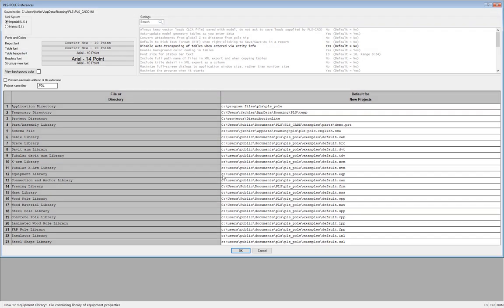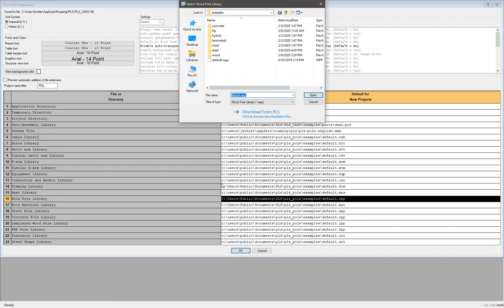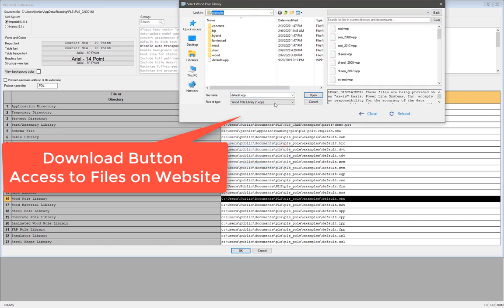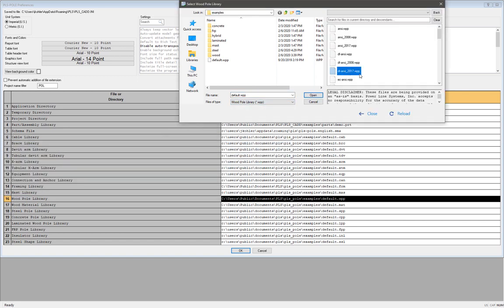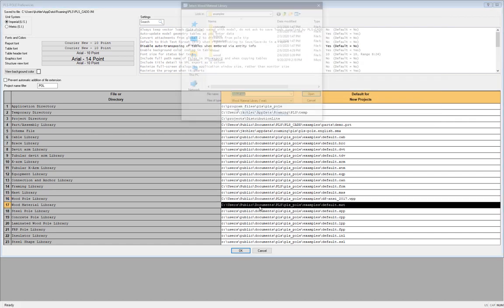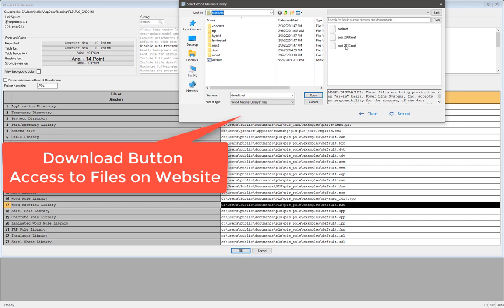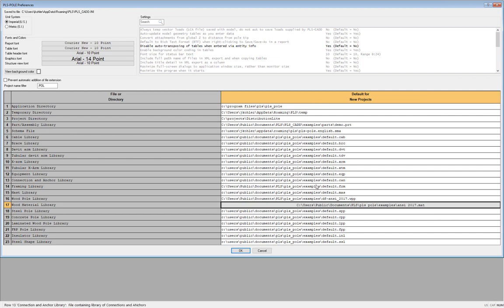To begin, we are going to launch the PLS pole program, and we'll first need to load in some library files for things like the pole and frame sets by going to File Preferences. Here, I will need to select the wood pole properties file for things like the height and diameters of the poles, and I'll click this button here to go out to our website and grab the latest Douglas Fir ANSI library. Then, I'll do the same thing for the wood pole material library, which has the flexibility and strength properties for the different wood pole species, and I'll pick the latest ANSI library there.